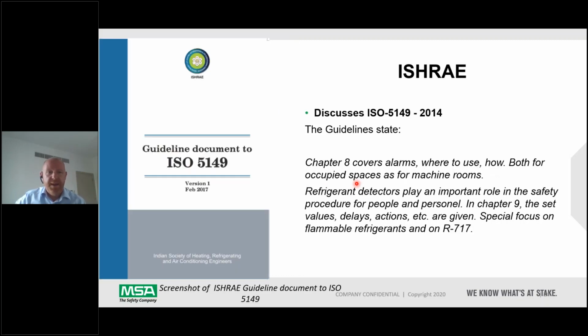The other ISHRAE guideline is a more recent one, ISO 5149, and this is just a screenshot of the front of the guideline. It says refrigerant detectors play an important role in the safety procedure for people and personnel, and it highlights that Chapter 9 of the ISO guide shows the set values, delays and actions needed to design the system properly, and it focuses on the new flammable refrigerants and R717.